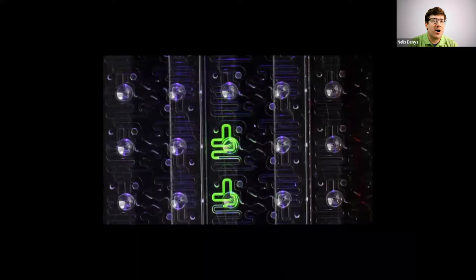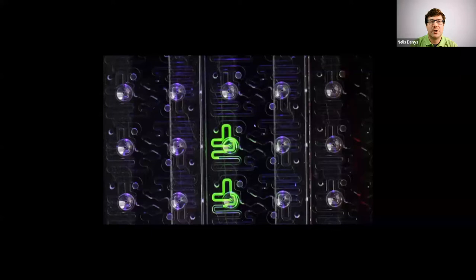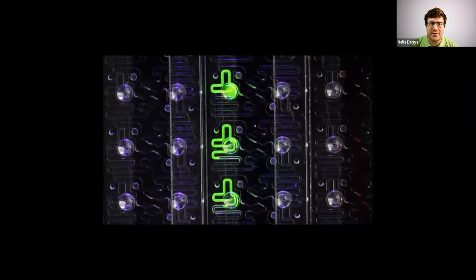Now, how does all of that work? We have a special consumable and here we can see exactly what sample loading looks like with the help of some fluorescein and a black light. In two wells, you can see that we already added two microliter fluorescein. And as you can see, to load another sample, you just simply add in two microliter in that input well, and the sample will just wick into the plate.